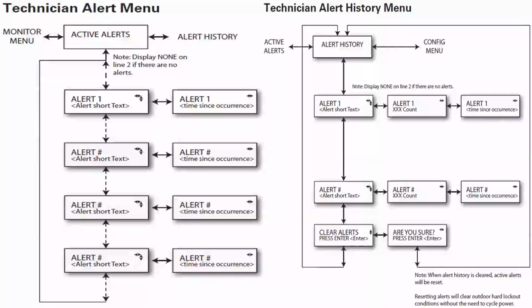Okay, so from monitor menu, we scrolled one right to active alerts. And it's going to give us our active alerts that we can go through and log down, right? So if we're communicating thermostat, we always want to log what we see on the outdoor unit. And on a communicating thermostat, we're going to go into alert history too, and it's going to give us an explanation of the alert and possible causes.